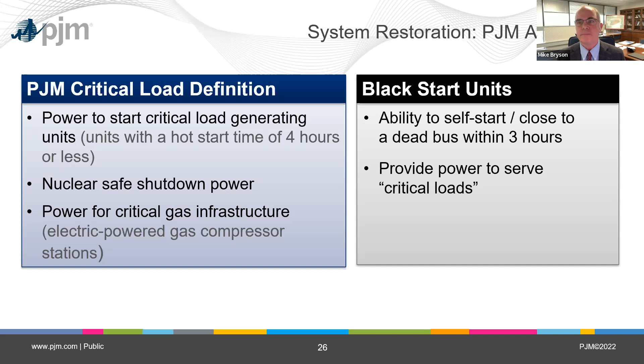So, just talking through the black start process, Paul touched on this, but it's really about bringing those black start units on across the system. We will start from as many of the 150 black start units we have across the system and start connecting them to the cranking paths from those black start units out to critical load, based on all of our individual utility restoration plans.